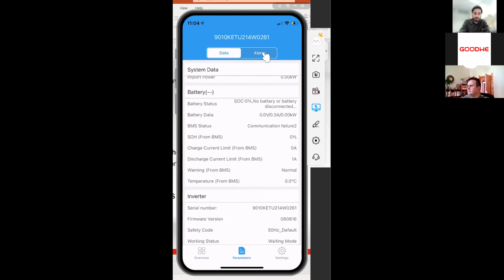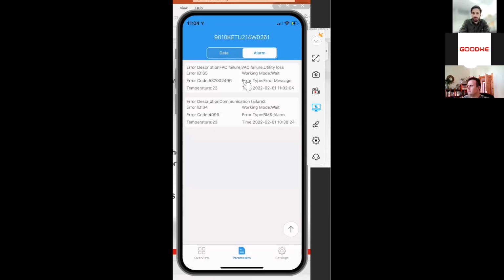Clicking on alarm here, we can likely see why we have a fault on our inverter. So here you see the history, and here you can also see we had earlier a communication failure with maybe... I didn't connect the Wi-Fi module tight enough. Or no, here it says BMS alarm, so the battery is not connected. Yeah, that makes sense.